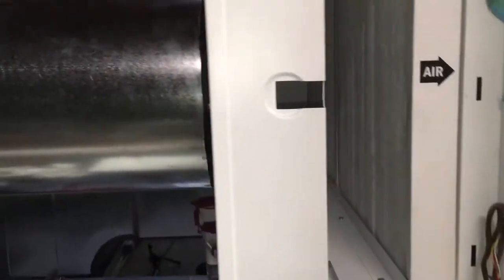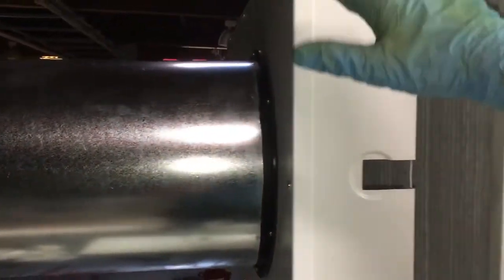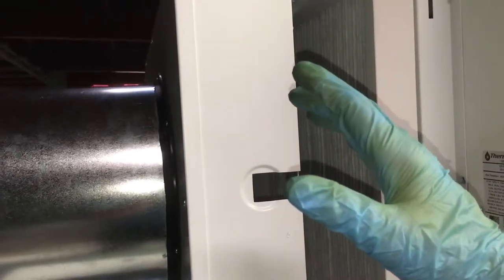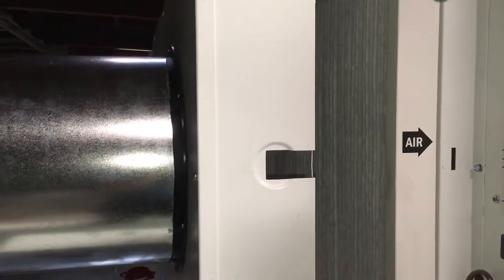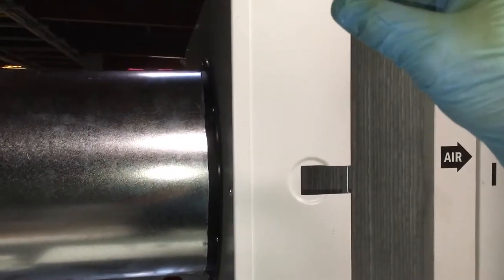That's why it's very important to insulate things when you have great differences in temperature and you have a high dew point. This is the result. You would have a lot of rust and water dripping everywhere if you don't insulate your ducting.